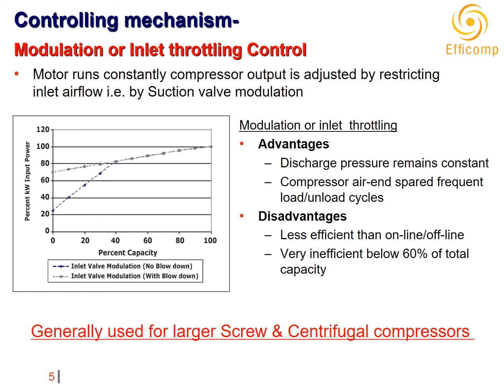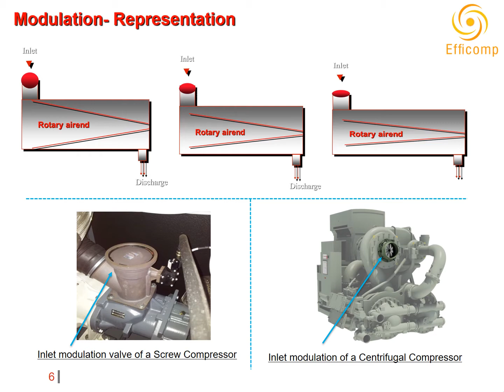The figures in the slide show the modulation mechanism wherein the inlet valve is throttled to reduce the intake air capacity, which is directly proportional to the compressor output. The discharge pressure is measured with a pressure transmitter, which then transfers a signal to the compressor PLC, which in turn controls the inlet valve operation. The inlet modulation valve may be pneumatically operated or electrically operated. Pictures show inlet valves in screw and centrifugal air compressors.